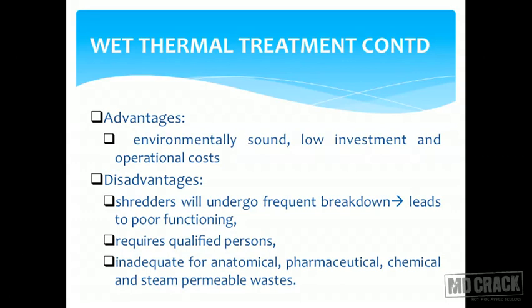Disadvantages of the wet thermal method: shredders will undergo frequent breakdown, which leads to poor functioning of the wet thermal process. It requires qualified persons to maintain the shredder, and it is inadequate for anatomical, pharmaceutical, and chemical waste, as they are not permeable to the heat.